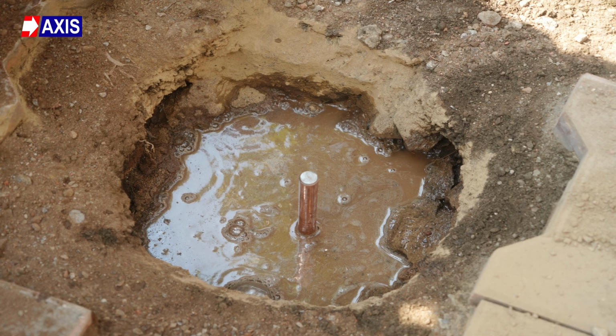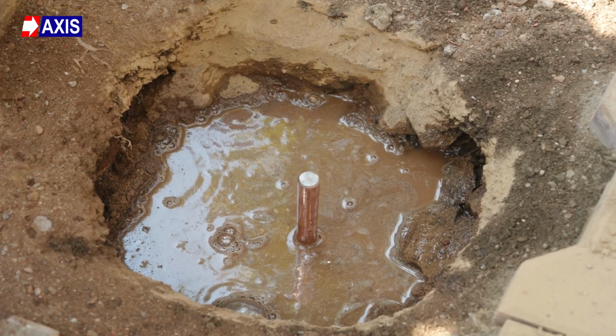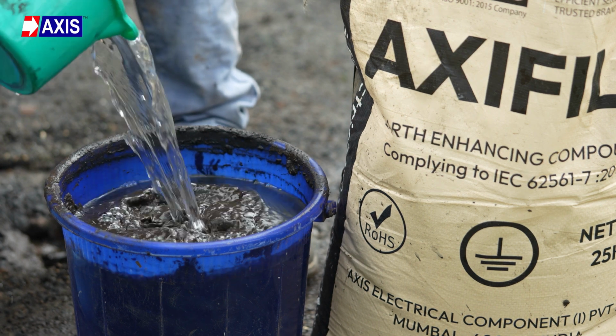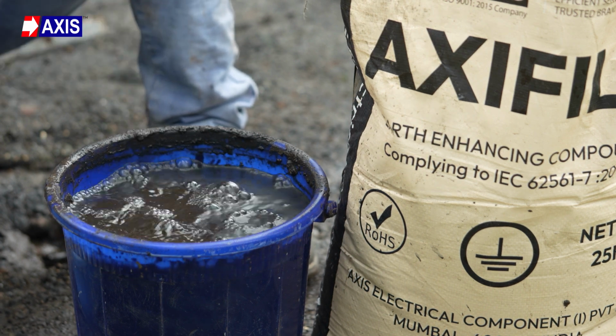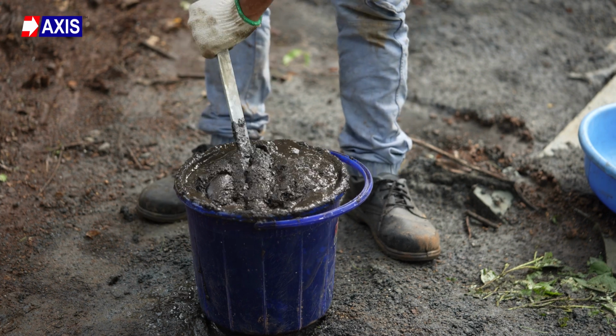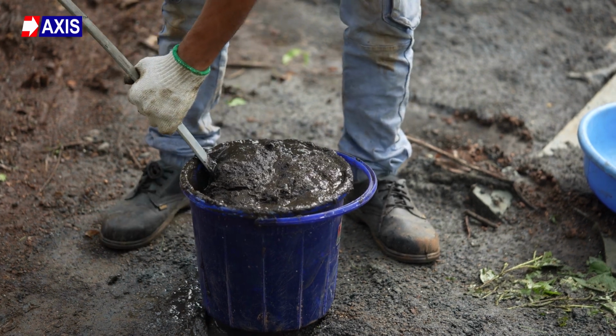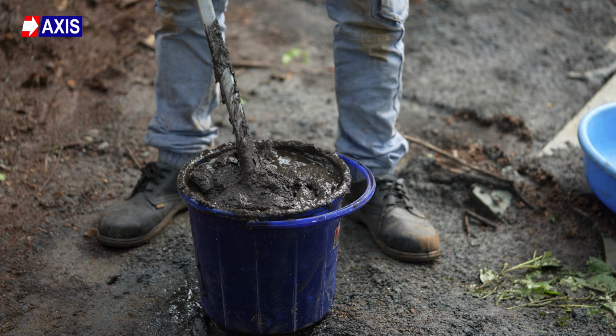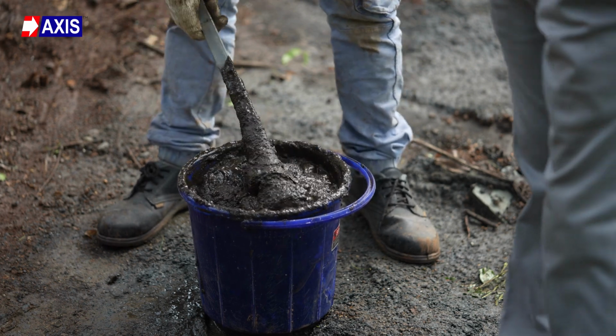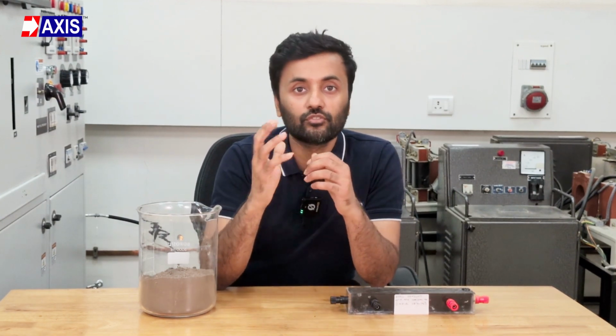Now this matters in earthing because your earth-enhancing compound stays in direct contact with your earth electrode for years. During installation, you mix the compound with water in the right ratio to prepare a slurry which looks like this. And this slurry has properties to retain water for a longer period, so your earth electrode stays in contact with moisture. This earth-enhancing compound slurry forms an electrolyte solution containing dissolved ions. These ions help conduct electrical current between the electrode and the surrounding soil.